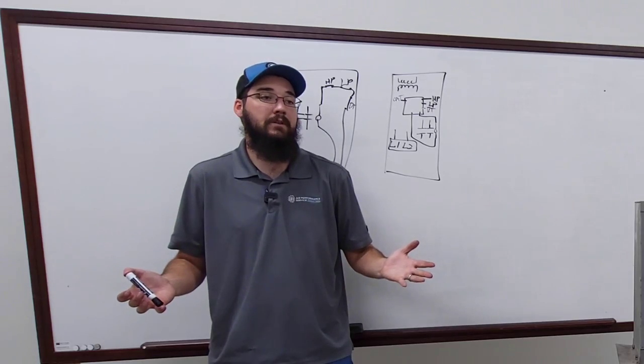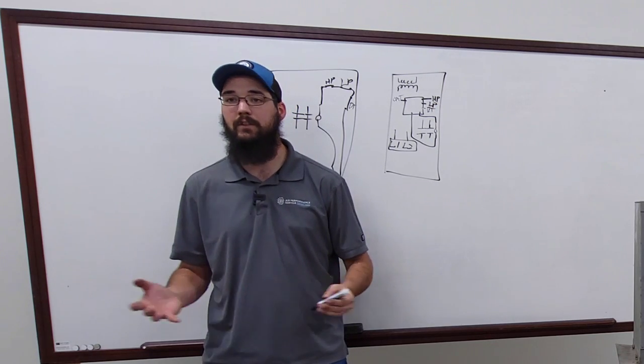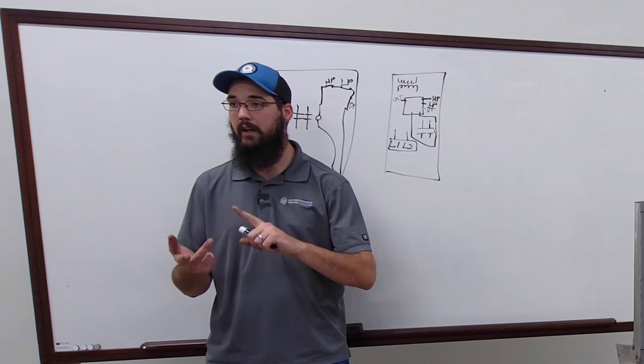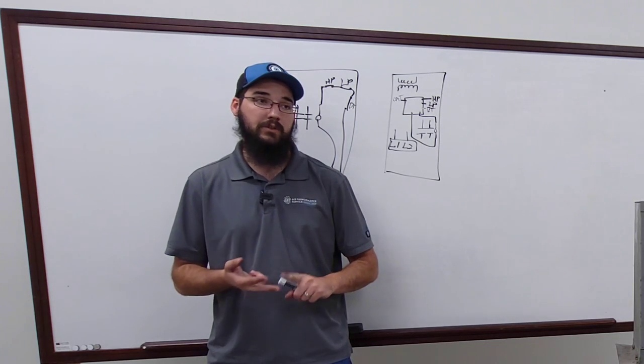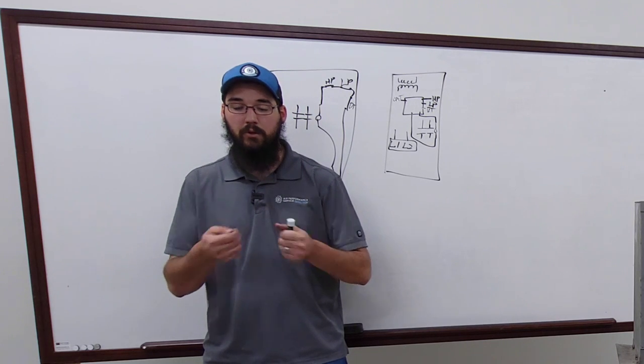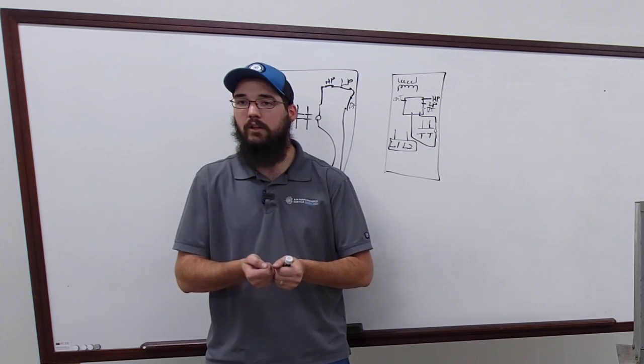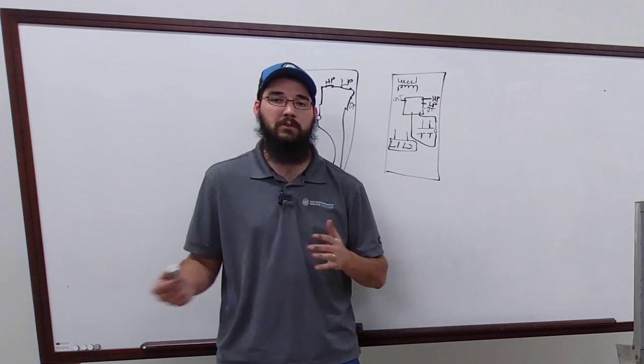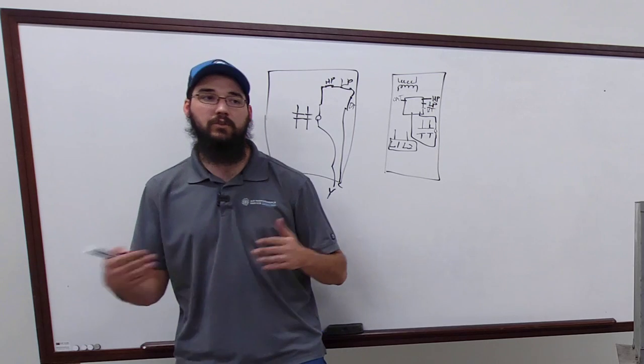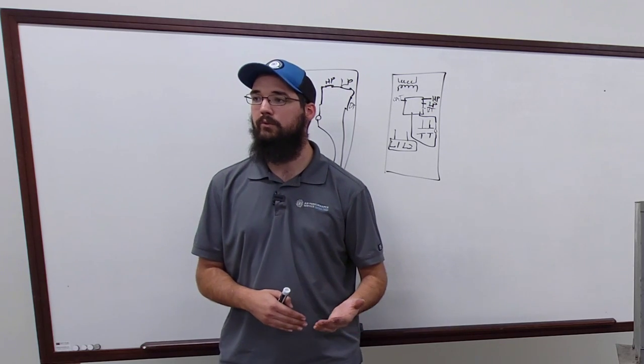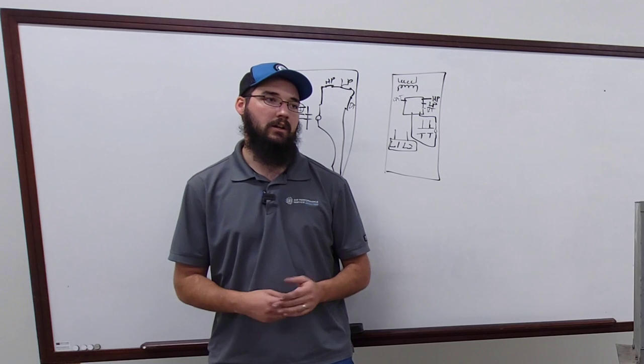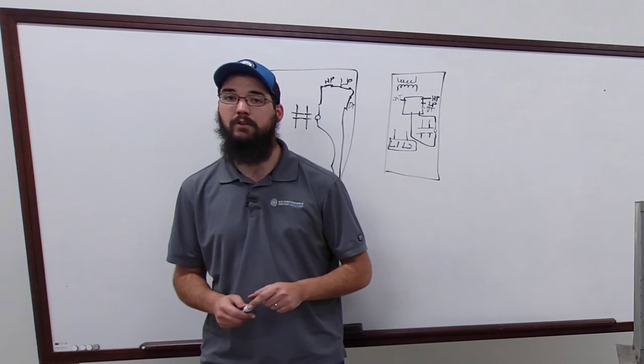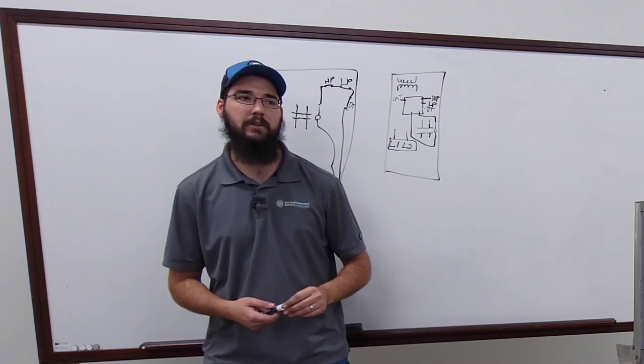Another example: we've got split systems out there that have ECM motors now as condenser fans, and that all goes back to efficiency and low ambient control. You can't even just ohm out the motor like you normally would — it's not a PSC, a permanent split capacitor motor anymore. Those are little things we're cycling over to. If you don't have a Zebra ECM tester, I highly recommend you look at investing in one. They're about a hundred bucks last time I looked. Those are types of tools that are going to become your common.